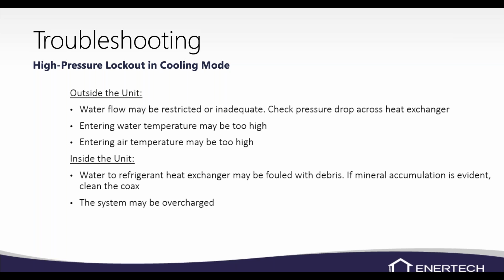we need to clean it out. The system could be overcharged. So if somebody, again, has been messing with the system, they've changed the TXV or something, it's possible that there's too much refrigerant in it. It would take quite a bit to overcharge the system and cause a high pressure lockout, but I've definitely seen that in the past. Obviously, a TXV issue, so blocked or seized TXV, or again, the high pressure switch could be faulty, or you could have a board issue as well.